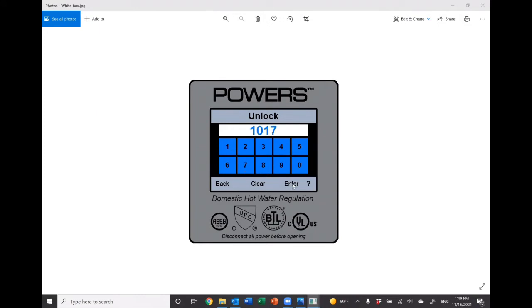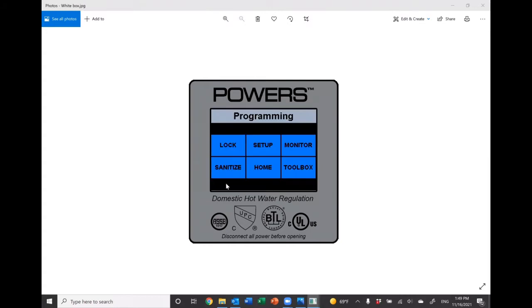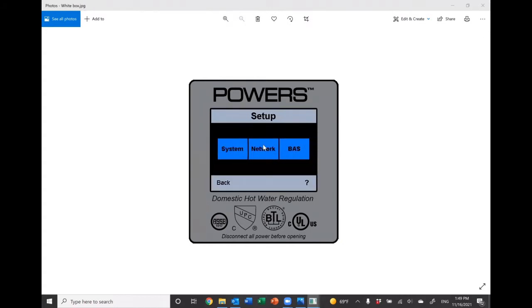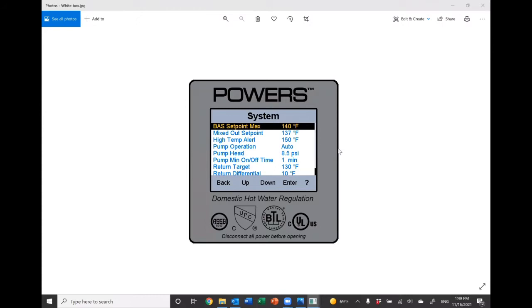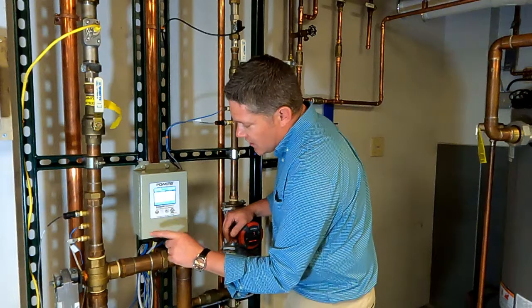Once you enter the password, you hit enter, accept the danger warning, go to setup, system. Here in the system screen, we have the mixed outlet set point. We have a high temp alarm. We have the pump operation, which can be on, off, or auto. We'll talk a little bit more about that. And we've got the pump head that you're going to want to set, and the pump minimum on/off time if you are going to have it on auto, to where the controller is turning that pump on and off when it doesn't need to be recirculating water.